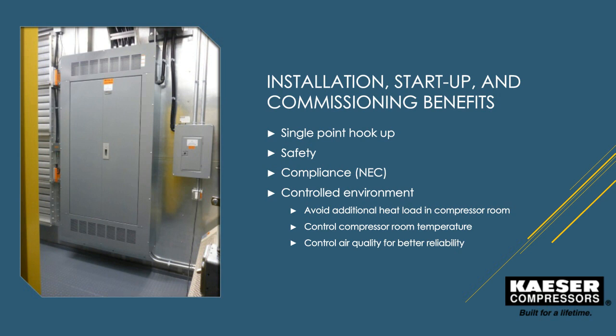First and foremost is NEC, or the National Electric Code, and I'm referring to the electrical spacing in front of all power distribution panels or control cabinets. Another one is OSHA, and that is in regard to the minimum clearance of walkways or the number and location of access doors.